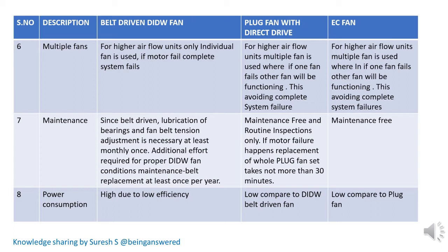For maintenance, since it is belt driven, lubrication of bearings and fan belt tension adjustment is necessary at least monthly. Additional effort is required for DIDW fan, and there are some parts which need to be replaced yearly. Whereas in the plug fan, it is maintenance free with routine inspection only, and if a motor failure happens, replacement of the whole plug fan set takes not more than 30 minutes.